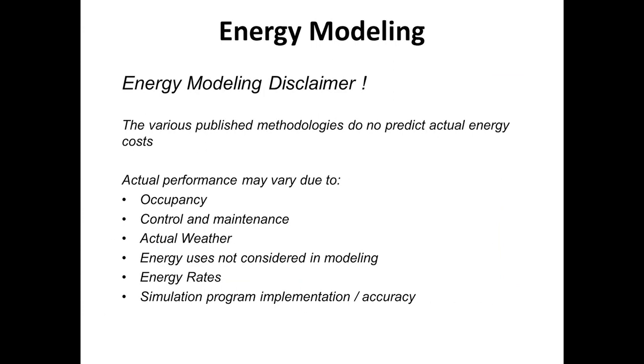Things like how schedules for occupancy affect energy use in the building, how the building's controlled, what resets are built into the control system, how the building responds to actual weather data. You can plug in things like energy rates and also use it to show in an existing building what the existing conditions are, and also tweak inputs, such as increasing the efficiency of a boiler and seeing how an increased thermal efficiency in the boiler affects the overall energy consumption of the building, or how a system redesign affects the energy consumption in the building.